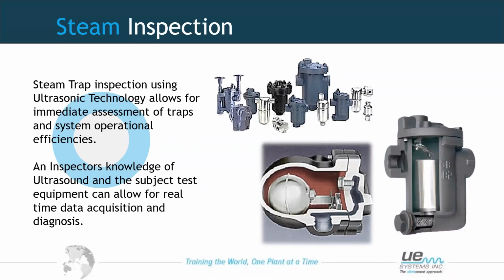There are different types of steam trap operations in place on sites, and we have our continuous flow and our on-off design. So we have our opening and closing mechanical traps and our continuous flow. So ultrasound will be used for mechanical based traps. If there is movement in there, we will detect the turbulent flow inside the system. And again, it's turbulence inside the pipework, so the ultrasound is trapped within the structure. So this is where we will actually listen using the contact approach.